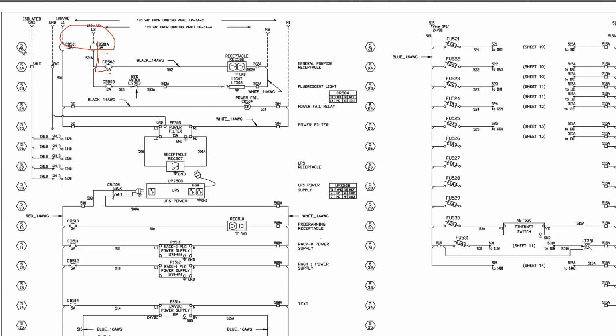These are line references. So 501, at least for this panel manufacturer, this is not universal. So don't take this as gospel for every drawing set you see. But it looks like this manufacturer, 501, lines up with the names of the devices. So you've got circuit breaker 501, circuit breaker 502 that lines up with these lines.